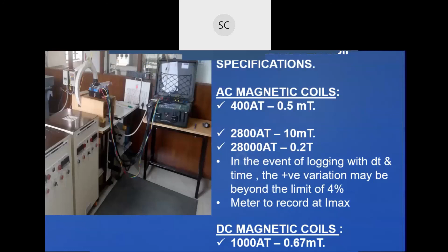2800 ampere turn is very important. So, at the time of procurement, the manufacturer is told that this is the ampere turn rate, and the ampere turn should be maintained. Because I have mentioned the ampere turn and the magnetic field strength, the gauge of the wire is also automatically fixed, as all of us know the formulas. Similarly, for the DC magnet, it should be 0.67 millitesla or 0.27 millitesla. In any circumstance, with any AC or DC magnet, the meter should record correctly.